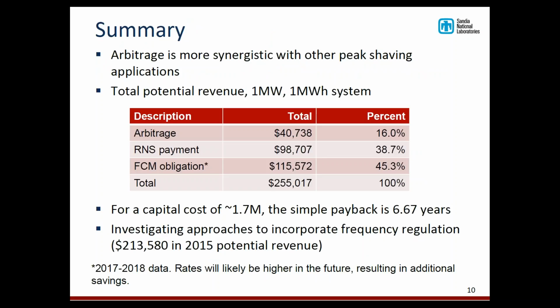So in summary, we've looked at several different potential revenue streams. Arbitrage, it turns out, is more synergistic with the two peak shaving applications because when you buy low, sell high, you're typically discharging during the peak hours. So we grouped those together, and the table shows the potential benefits for a 1 megawatt-hour system. So arbitrage was around $40,000, RNS payment was about $98,000, and the forward capacity market obligation was around $115,000. So that gives you around $255,000 for total potential expected revenue, and that's ignoring frequency regulation.